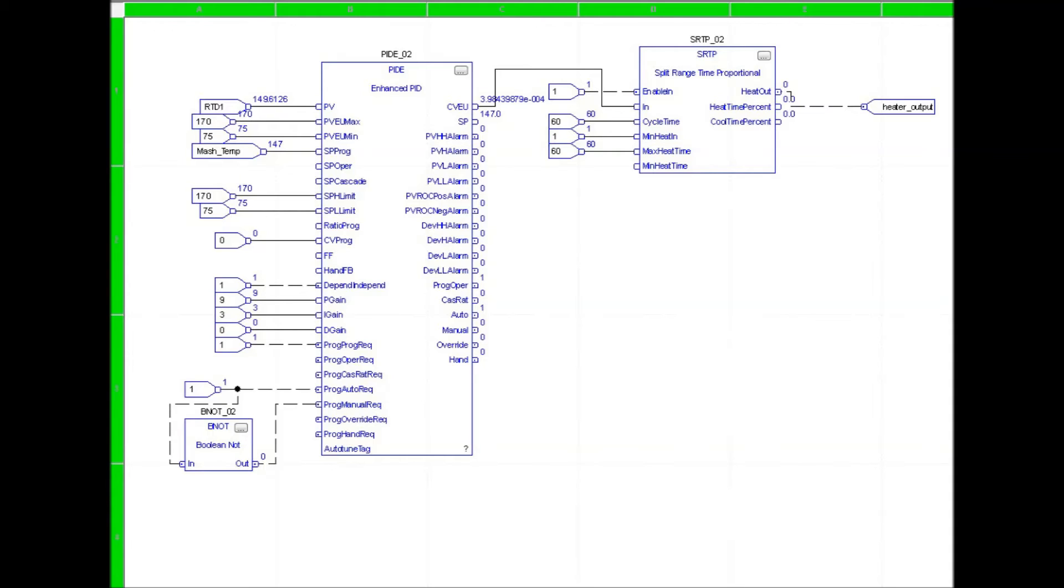Since the heating element is controlled with the solid state relay, it only has the option to be on or off. The time proportional instruction takes a percent output and changes it to a time on. For example, if the cycle time was 10 seconds and the output of the PID was 60%, the SRTP instruction would send the output to the relay to switch on for 6 seconds and then off for 4 seconds.